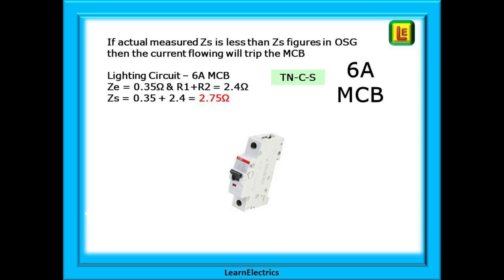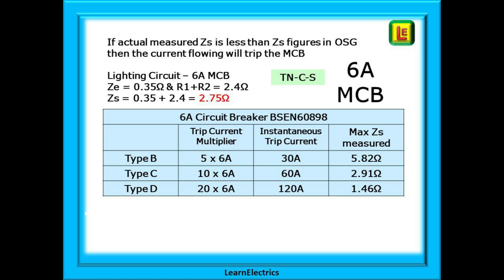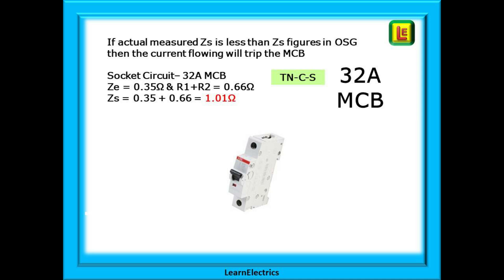If we use a lighting circuit as an example, a 6 amp MCB is to be installed. The ZE is 0.35 ohms and R1 plus R2 is 2.4 ohms. Adding these together, we have 2.75 ohms for ZS. If we now look at the maximum ZS values for the 6 amp types, we can see that at 2.75 ohms, the actual ZS is well below the maximum of 5.82 ohms for a type B breaker and just below the maximum limit for a type C. Both the types B and C 6 amp breaker will operate correctly. However, the type D does not meet the criteria.